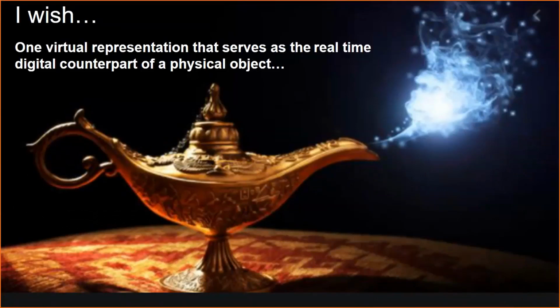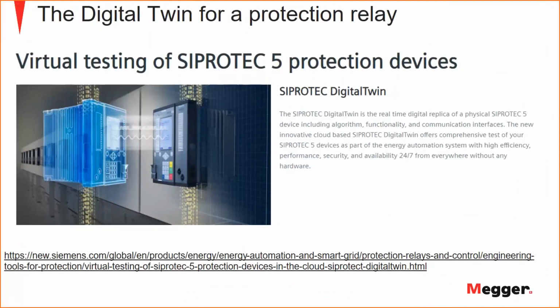And that is, I wish to have a virtual representation that serves as the real-time digital counterpart of the physical object. I would like to have a digital copy of that relay. I would like to have a digital copy of that test set and put them together. This is actually a definition of a digital twin. So the digital twin is a digital copy of that physical device. And SIPROTEC 5 from Siemens has done this since 2 years ago, and we have been contacted, and we developed something similar. I will say later. Virtual testing on SIPROTEC 5, they call it digital twin, and it's a digital copy available of a SIPROTEC 5 device.